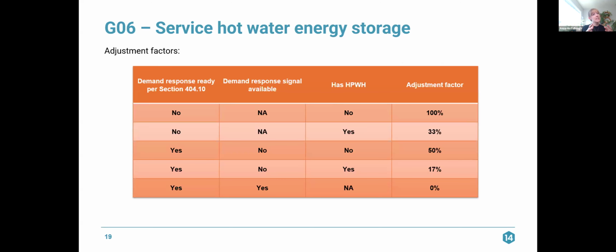And these are the adjustment factors. So this is really similar to the table that we looked at for the HVAC shift, HVAC load shedding credit. So is your building required to be demand response ready per section 404.10? Yes or no? We'll go through that in a second. Is the demand response signal available from a controlling entity like your utility? Does it have a heat pump water heater? And then you get your adjustment factor. So we'll say it is not required to be demand response ready. It does not have a demand response signal available, and it has a heat pump water heater. So you would adjust your credits by 33%.